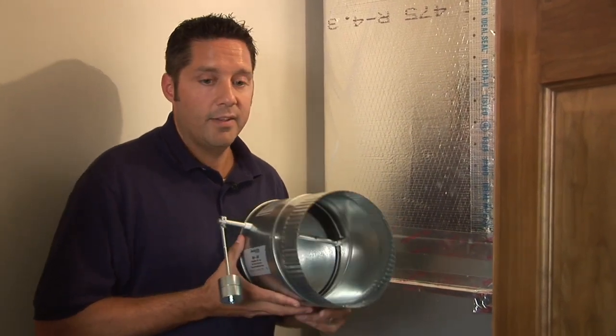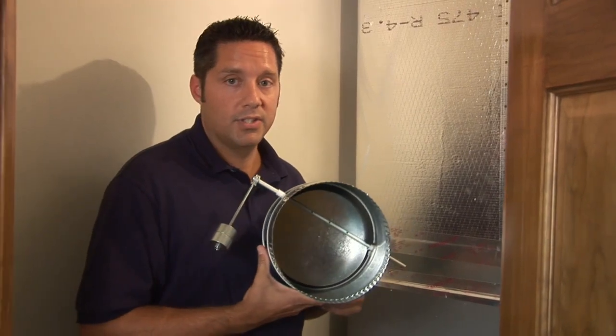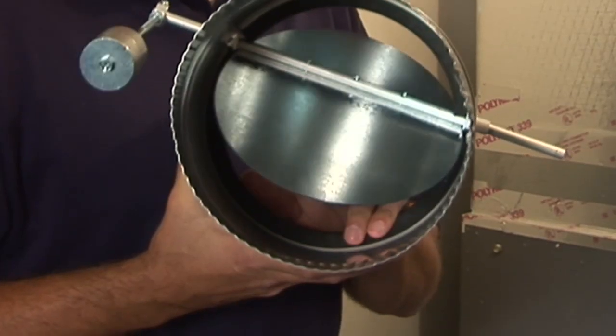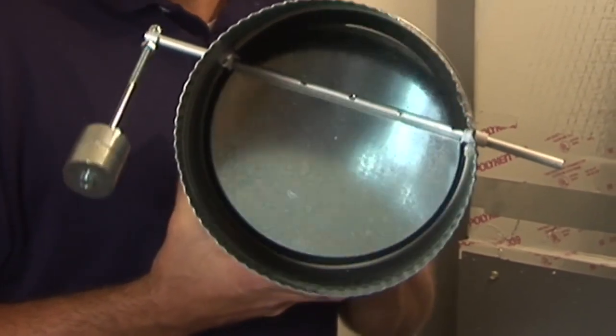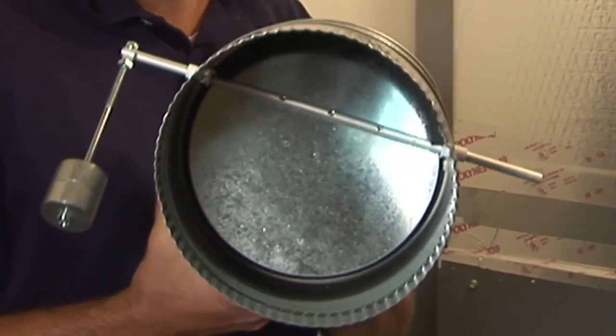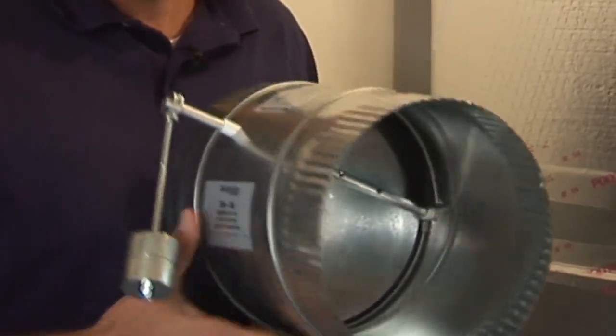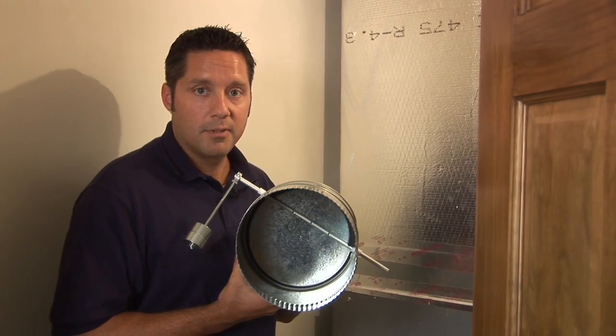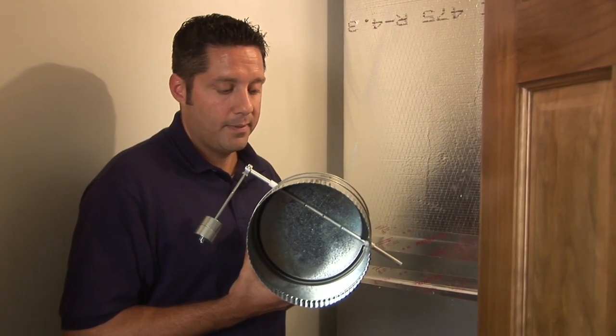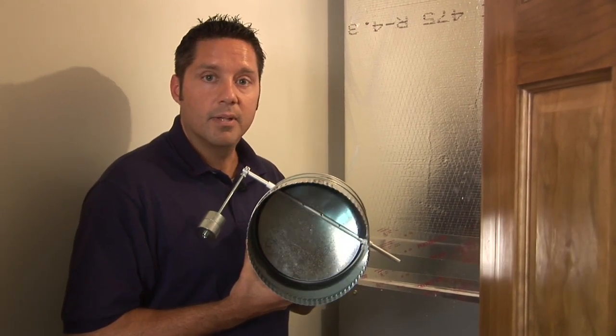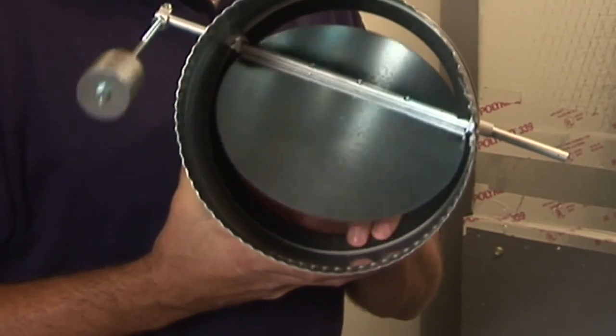So as we have an area of the home that we don't want to supply conditioned air to, we're going to power the actuator on the zone damper, power that close, and this bypass damper is going to naturally open up. It is just a weighted arm assembly on this barometric bypass damper, and as the static pressure rises, the blade's going to naturally open itself open and try to equal out the system.